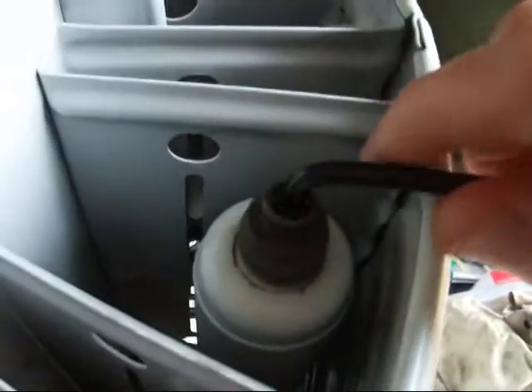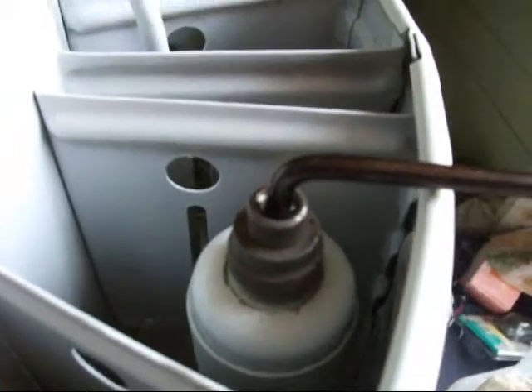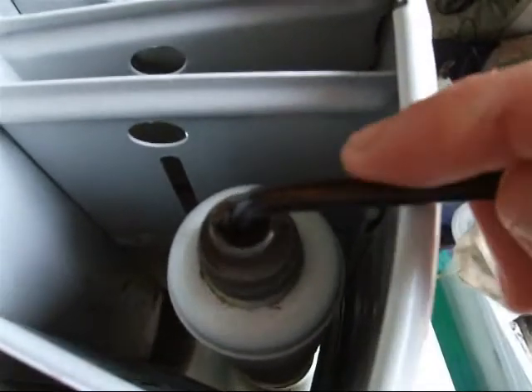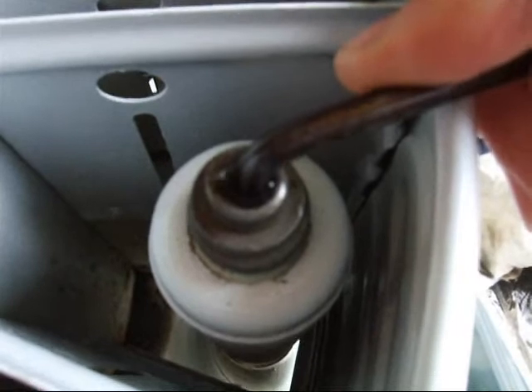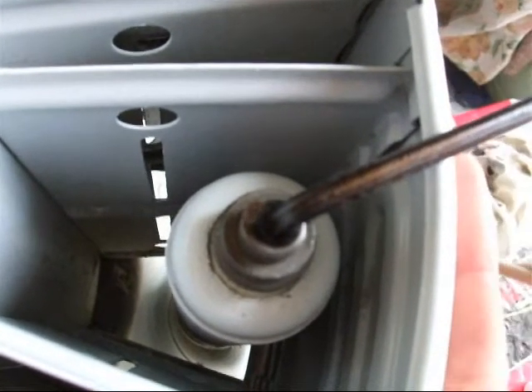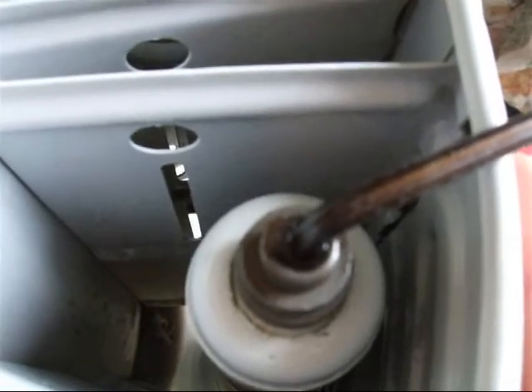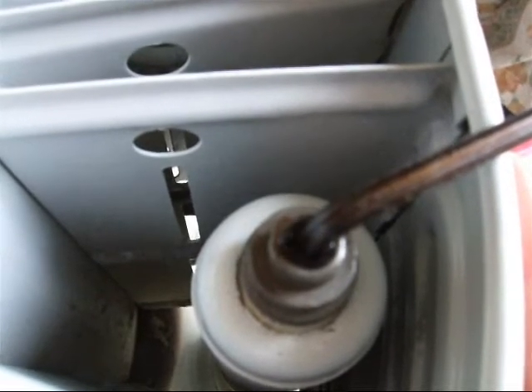Now I'm going to try opening the valve and we'll see which way the oil goes. I've loosened the valve — see that bubbling there? That's what we want. It's bubbling, but not so fast as to blow the oil out. You don't want to do that because you run the risk of losing methyl formate.